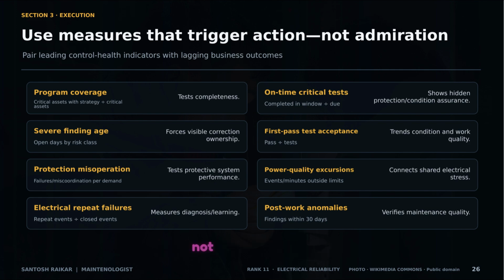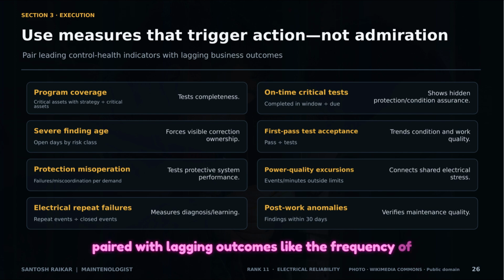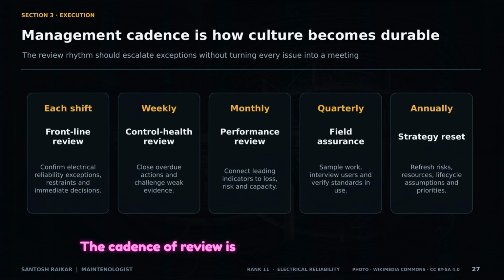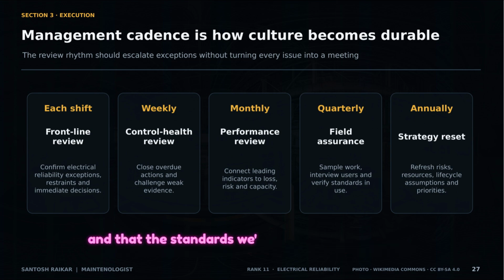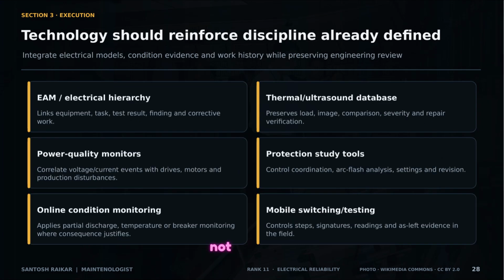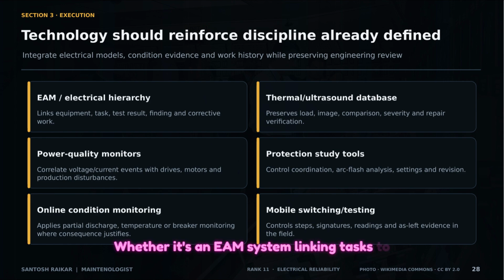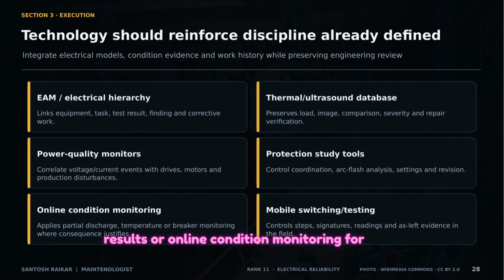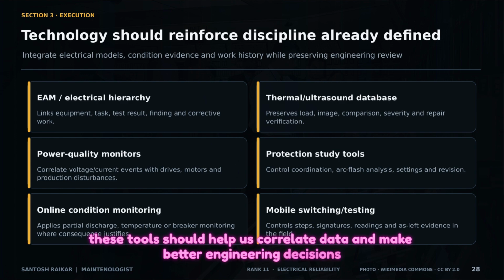Metrics should trigger action, not just admiration. We need leading indicators like the percentage of critical tests completed on time, paired with lagging outcomes like the frequency of protection misoperations or repeat electrical failures. The cadence of review is how culture becomes durable, from quick shift reviews to annual strategy resets. This rhythm ensures that exceptions are escalated and that the standards we've set are actually being followed in the field. Technology should support our discipline, not replace it. Whether it's an EAM system linking tasks to results or online condition monitoring for high-consequence assets, these tools should help us correlate data and make better engineering decisions.